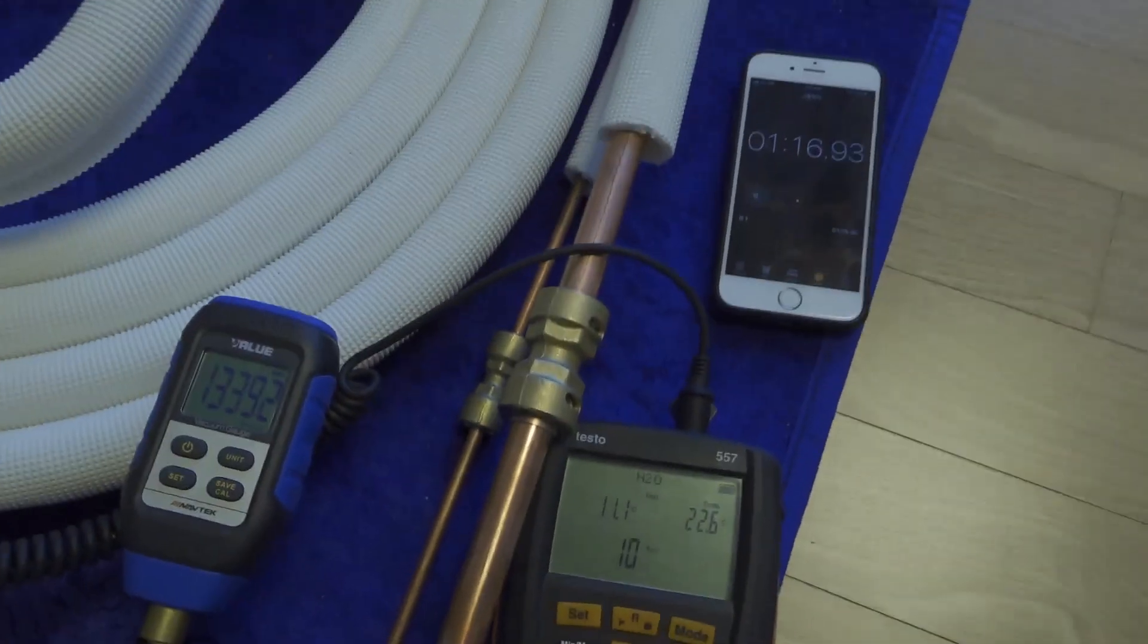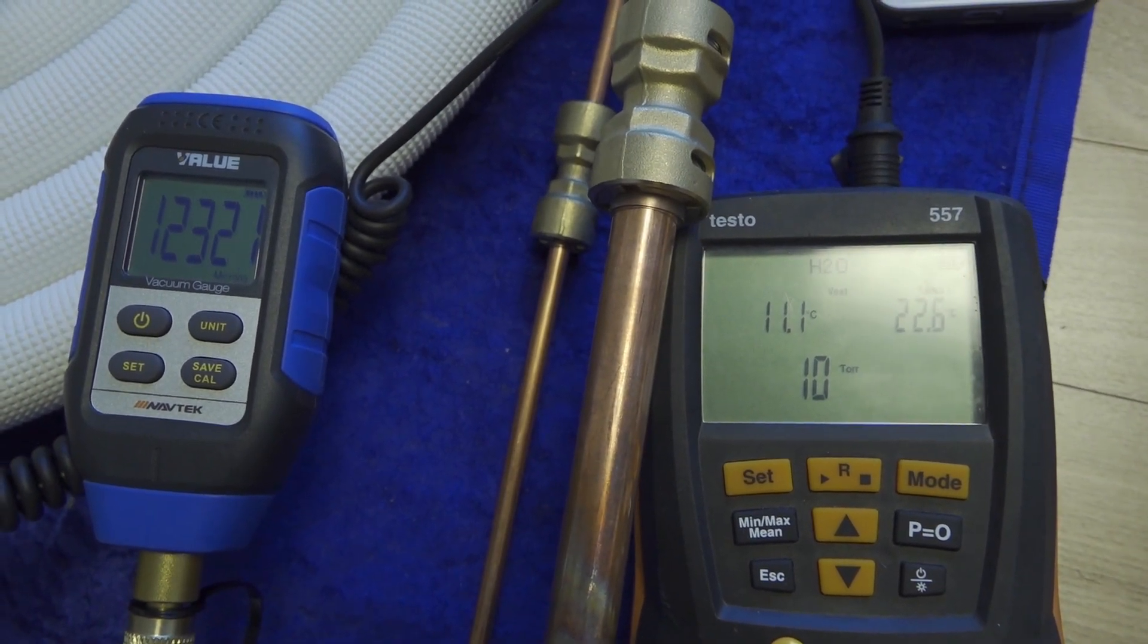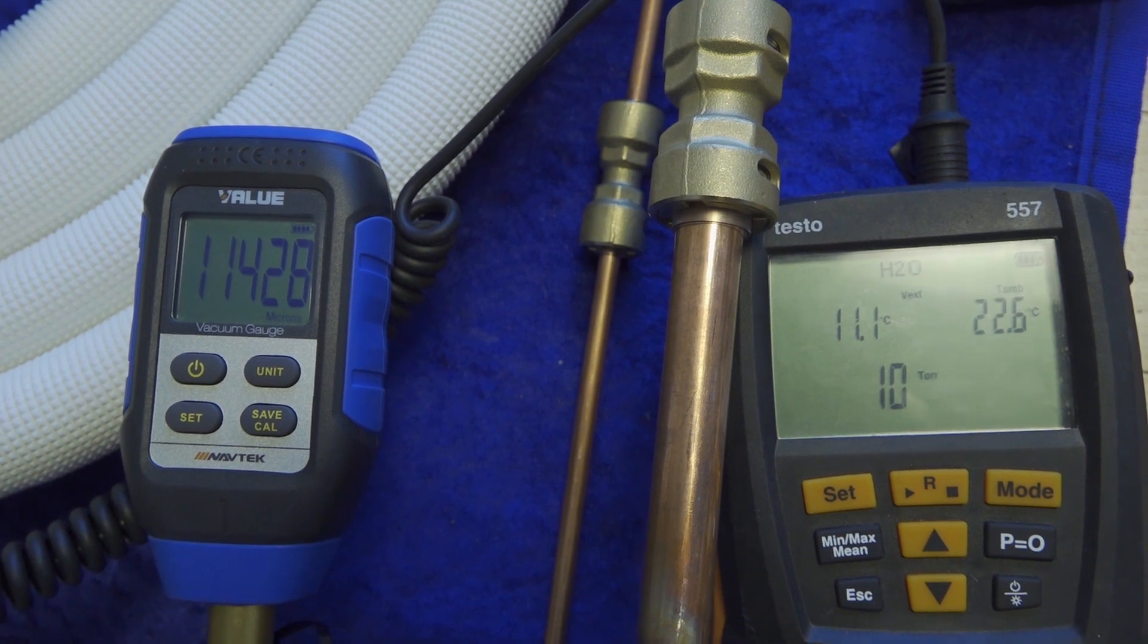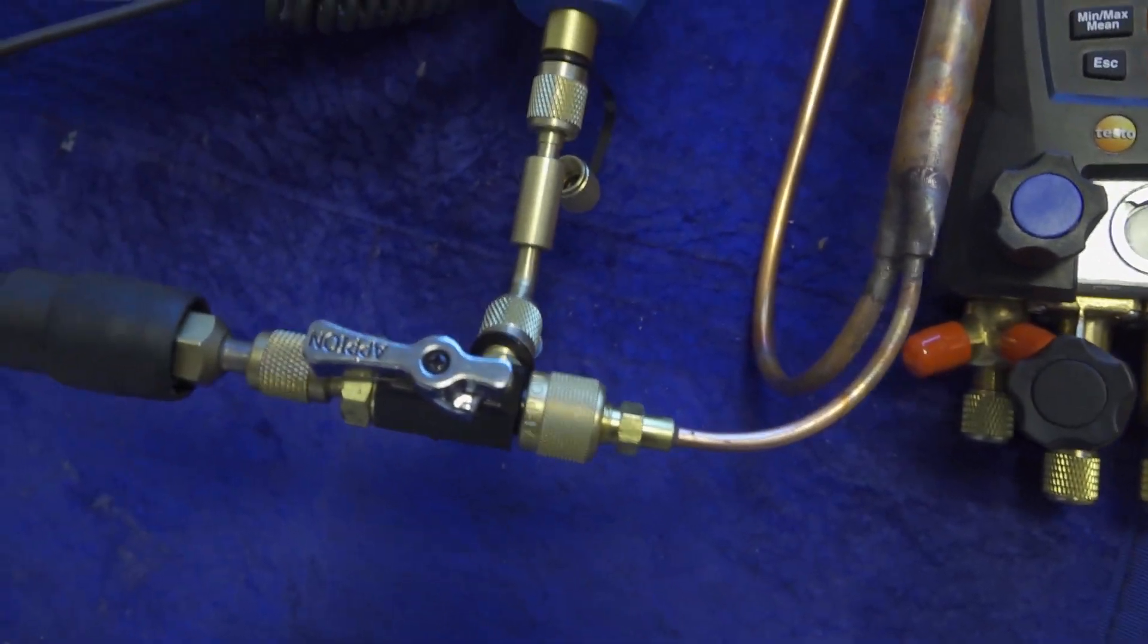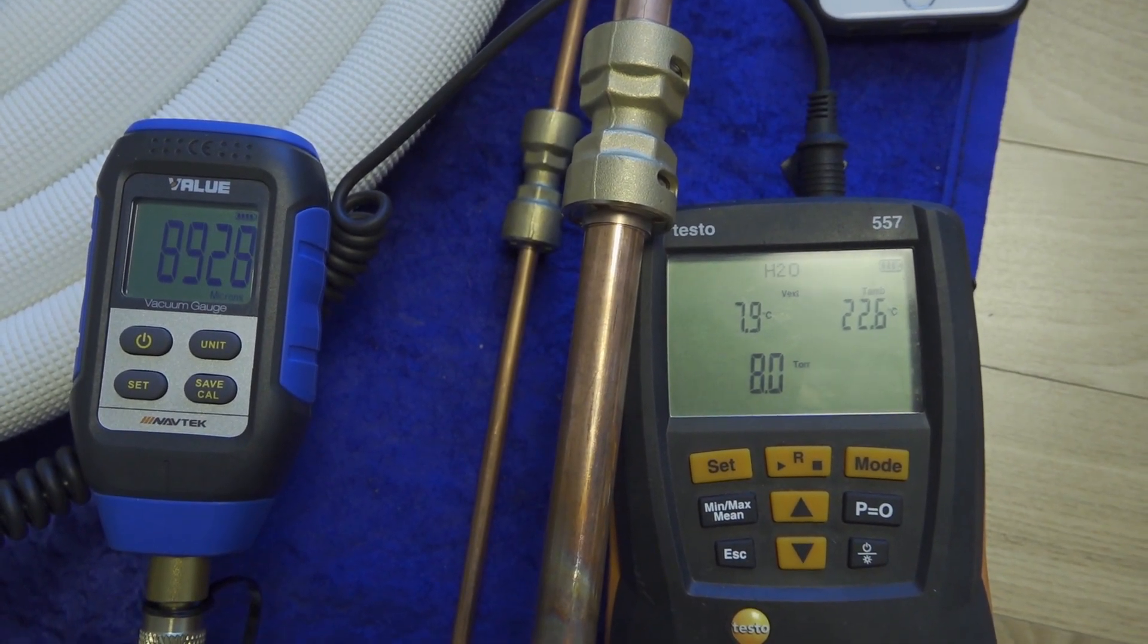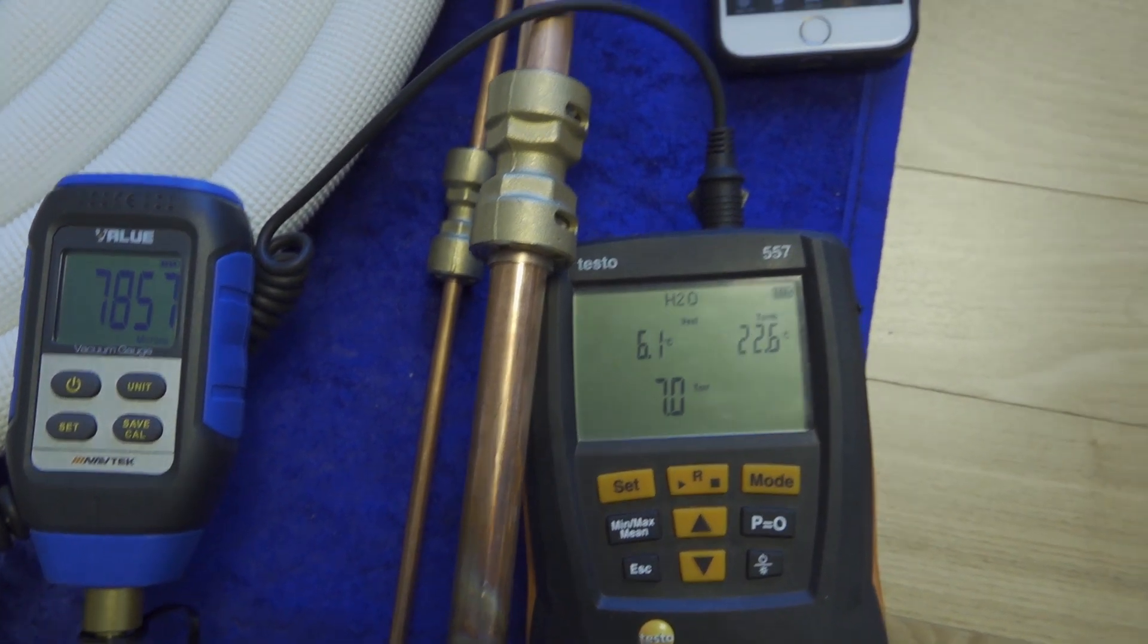Now let's look at the digital side. It's currently at about 10 Torr and progressing. I'm checking the vacuum at the 8m end. There's quite a bit of difference between the two readings. They don't read exactly the same. The elapsed time is about 1 minute 40 seconds.